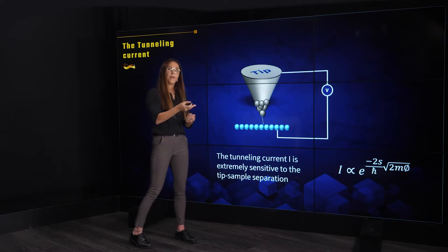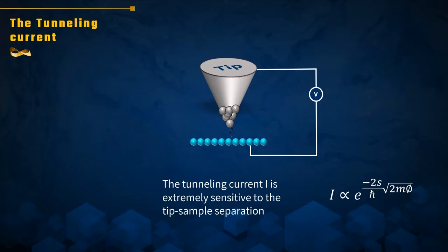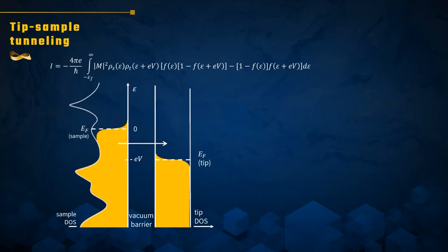This tunneling current is an extremely sensitive probe — it depends exponentially on the distance between the tip and the sample — and this is what allows us to measure height variations on the order of a fraction of an angstrom and to image the surface of the material down to atomic resolution. As for the lateral resolution, from the same reason the tunneling current is extremely local: it occurs from the last atom at the end of the tip, and therefore it allows the lateral resolution needed to measure atomic-scale features of the surface.